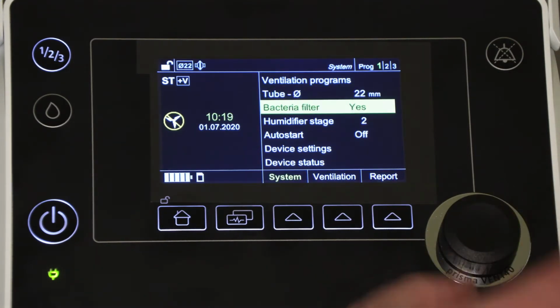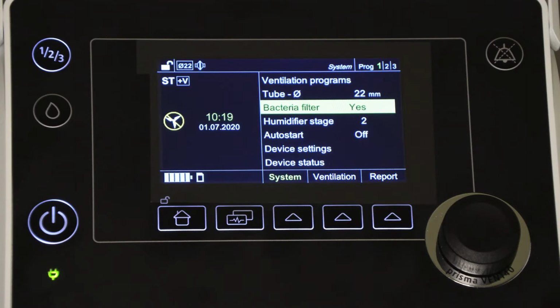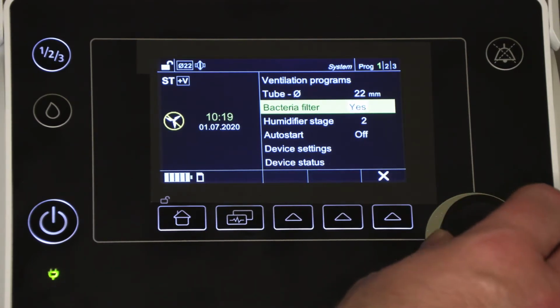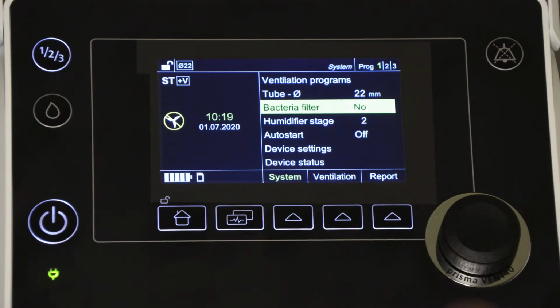The bacteria filter setting enables the device to know that a bacteria filter is being used and ensures that the generated flow and pressure will allow for this. In the clinical setting, this is normally left in the on position. However, in some home settings where a bacteria filter may not be necessary, it can be turned off.